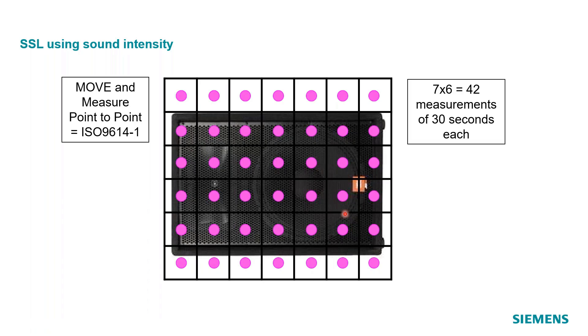And then we're going to move to this grid point, and we're going to make another measurement, and so on and so on until we fill up this whole grid. And we have a total of 42 measurements. Each of them is 30 seconds long. And so we've spent a significant amount of time making this measurement. So it's not a fast measurement by any stretch of the imagination, but we'll also be able to calculate the sound power.